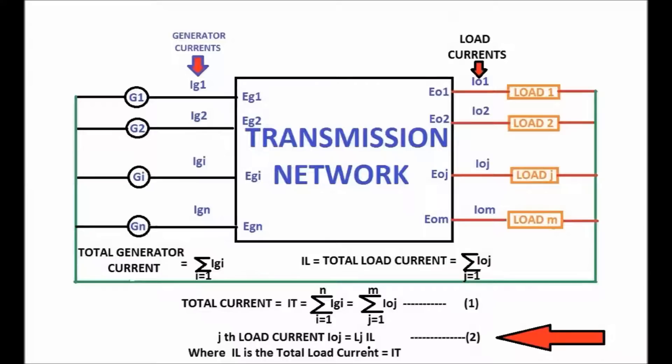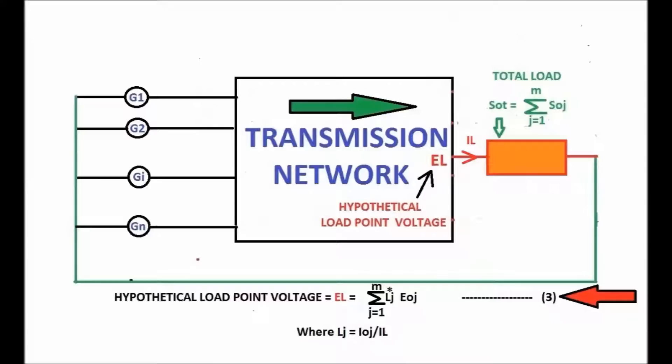The hypothetical load point voltage EL is arrived at after performing many matrix operations. The voltage EL equals the sum of the product of complex conjugate of the fraction Lj with the load voltage Eoj, as in Equation 3.